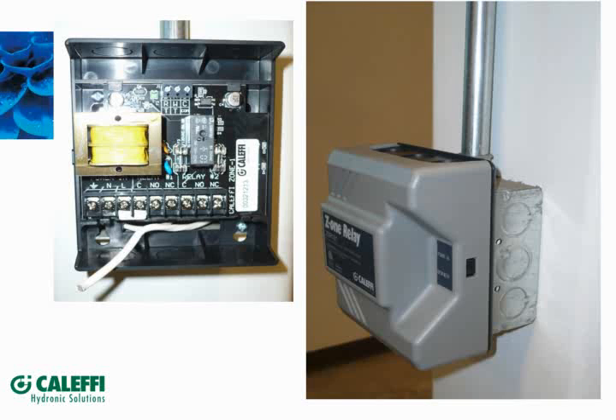So you could have that box in the sheetrock wall. They sheetrock, they paint, you come back, and now your relay box would flush mount to the wall and it would look really pretty. You wouldn't see that conduit or that box or anything because it would be hidden by the sheetrock and stuff. And even if they router around it a little bit big, because I know some sheetrockers use a router to go around those boxes, you can see the relay box covers the metal box by about a ½ inch or more on all dimensions. So if they get a little wild cutting it out, you still got a big enough back on the relay box to cover it, make it look really nice. So that was a nice.